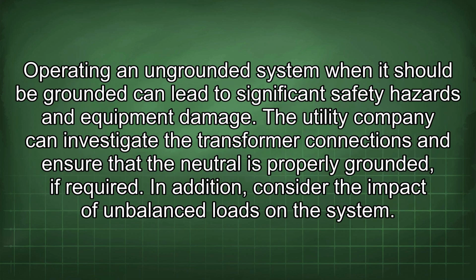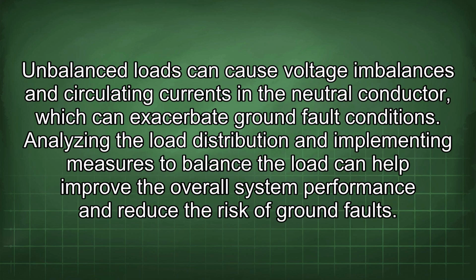Operating an ungrounded system when it should be grounded can lead to significant safety hazards and equipment damage. The utility company can investigate the transformer connections and ensure that the neutral is properly grounded, if required. In addition, consider the impact of unbalanced loads on the system. Unbalanced loads can cause voltage imbalances and circulating currents in the neutral conductor, which can exacerbate ground fault conditions. Analyzing the load distribution and implementing measures to balance the load can help improve the overall system performance and reduce the risk of ground faults.